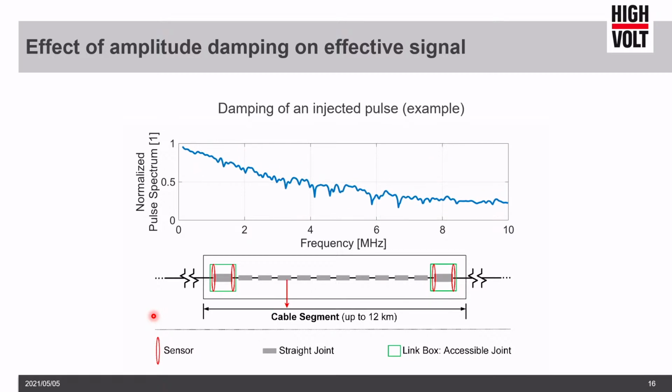And what we do is we inject this pulse. We do this several times a day, maybe several times an hour, it's not clear up to now, to get rid of every influence like heating, aging, and so on, which could change the transfer function. And maybe this also answers a little bit this question. If the transfer function changes, we might be able in the future, by collecting data, we are again at the big data buzzword, and then using methods of machine learning or artificial intelligence, to judge, okay, this cable is old or young. But if we don't start to collect all this data, combined with metadata, temperature, pressure, and so on, we will never be able to determine something and also to predict the future.